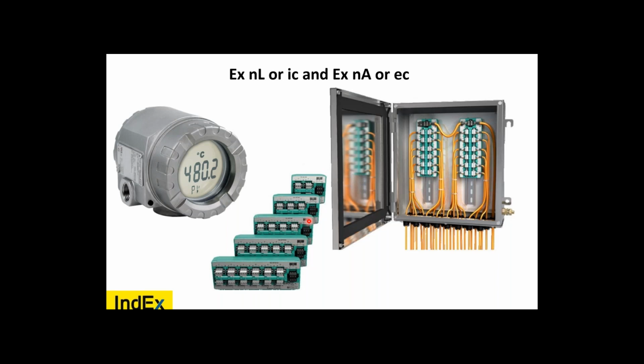Perhaps they know EXNL. Now, EXN used to be compliant under ATEX. EXN only, just mentioning an N, was acceptable as long as it was described in the certificate. But the problem is the manufacturers are not all equal.